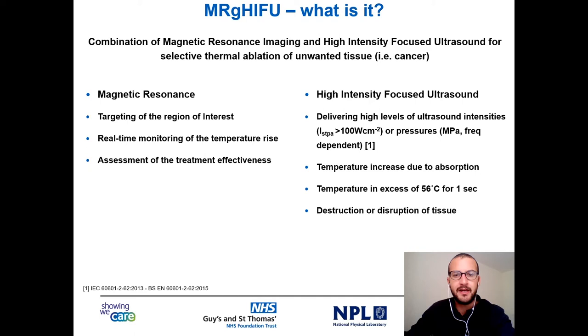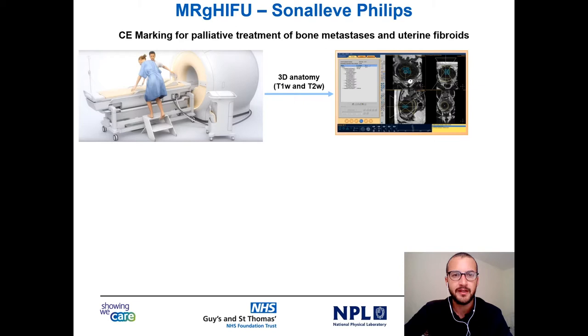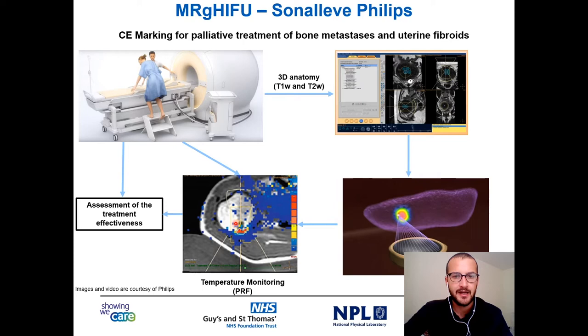At St. Thomas Hospital, we have a Philips Sonalleve, which is marketed for treatment of bone metastasis and uterine fibroids. As you can see, the patient is positioned into the MRI scanner, and an anatomical image is taken for treatment planning. The HIFU transducer delivers high-intensity focused ultrasound, while the MRI thermometry allows real-time monitoring of the temperature rise. Later on, you can take another image to assess the treatment effectiveness.